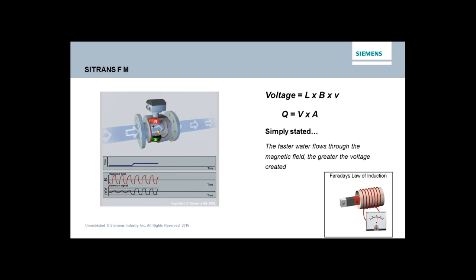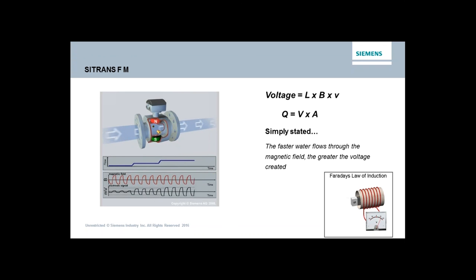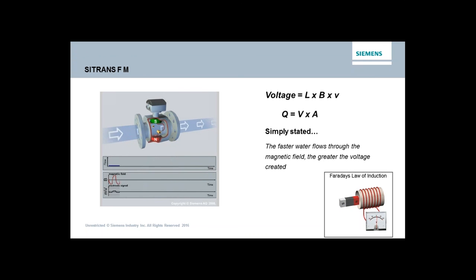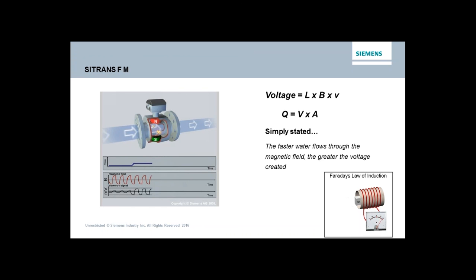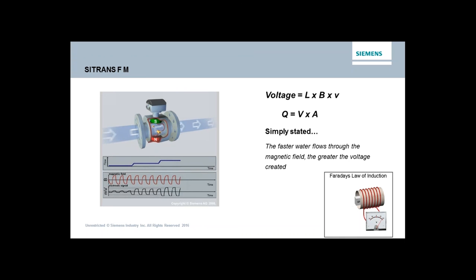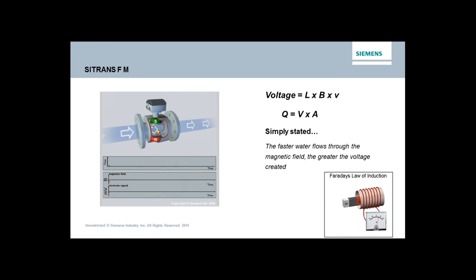So what is conductive material? Let me start by saying what isn't conductive enough — and that would be gas and steam. So this is not a technology to be used in gas and steam applications; it is a liquid flow meter. That having been said, it's a very flexible liquid flow meter in that it can have solids, it can have slurries, it can have all kinds of different things. It can even have a certain amount of entrained air in the liquid and still operate perfectly well.